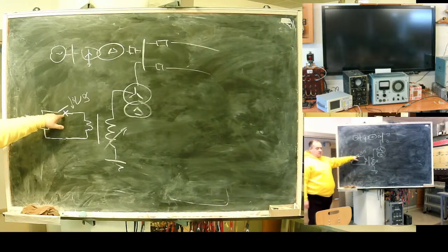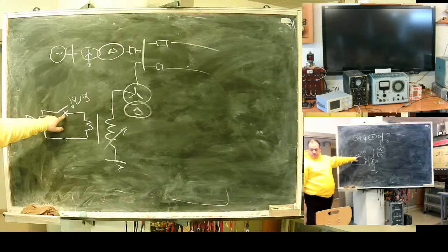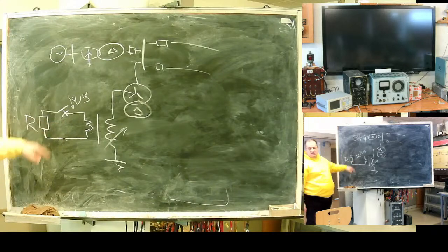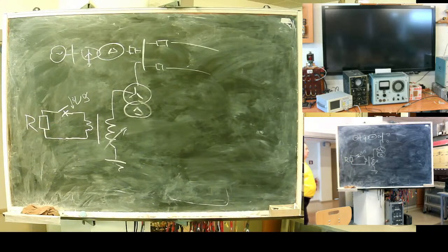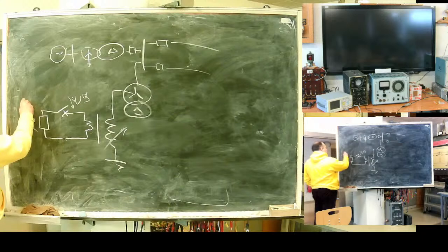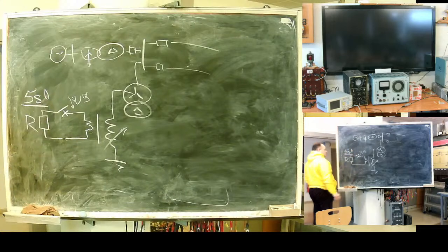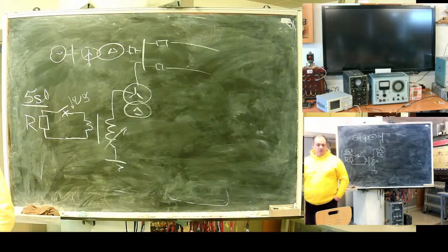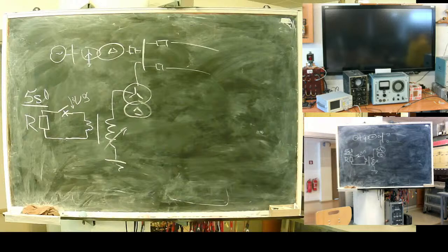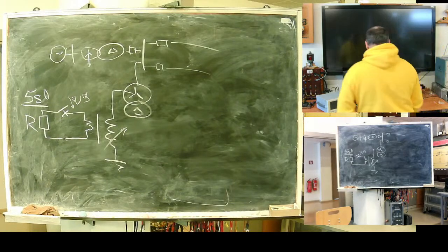This breaker will go on without protection, the fault remains, and this resistance will burn. It can only withstand fault current within 5 seconds. They are not thermally sustainable. It's a problem.